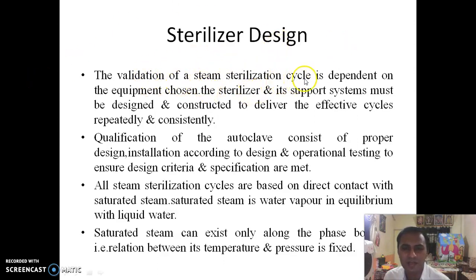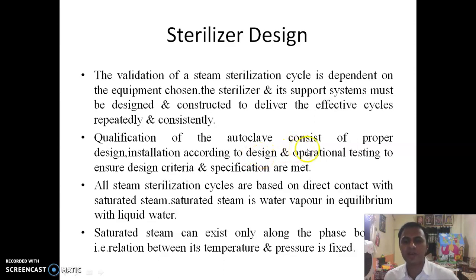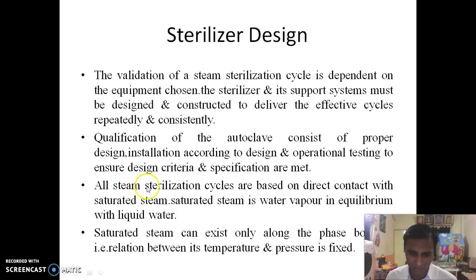The validation of the steam sterilization cycle is dependent on the equipment chosen. The sterilizer and its support systems must be designed and constructed to deliver effective cycles repeatedly and consistently. Qualification of the autoclave consists of proper design, installation according to design, and operational testing to ensure design criteria and specifications are met. All steam sterilization cycles are based on direct contact with saturated steam.